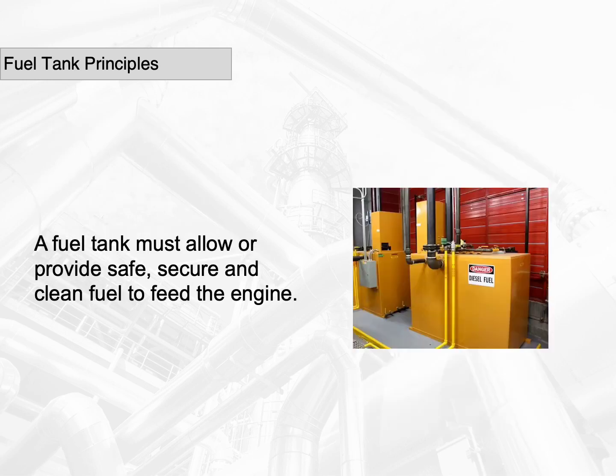Fuel tank principles. A fuel tank must provide safe, secure, and clean fuel to feed the engine. The tank must contain a given quantity, avoid leakage and limit evaporative emissions. Fuel tanks must be filled in a secure way, without sparks, provide a method for determining the level of fuel in the tank, provide venting, anticipate potentials for damage and protect against it.